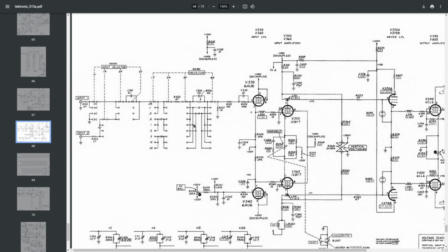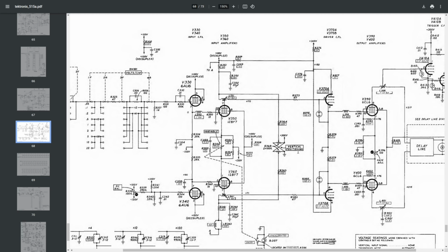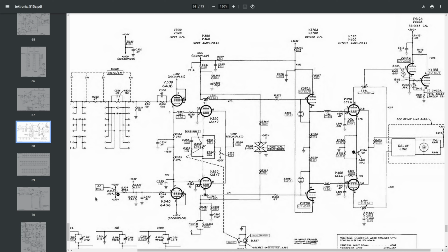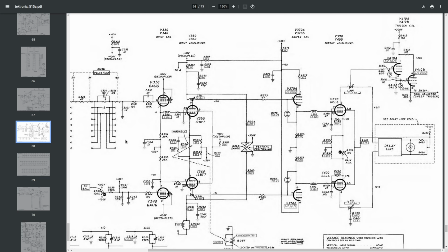So yeah, going back to our inputs, one input of our differential amplifier is the actual input of the oscilloscope on the front panel, and the other input goes to a potentiometer that cancels out the offset. So in an ideal world, all these tubes would be identical and the amplifier would have zero offset, but of course the tubes are slightly different between one another, which creates an offset, and with vacuum tube equipment it's really hard to get the offset down to zero, so we have an adjustment for this on the front panel. And we can cancel out the offset using this potentiometer right here, which is also on the front panel, and it can be trimmed using a flathead screwdriver.